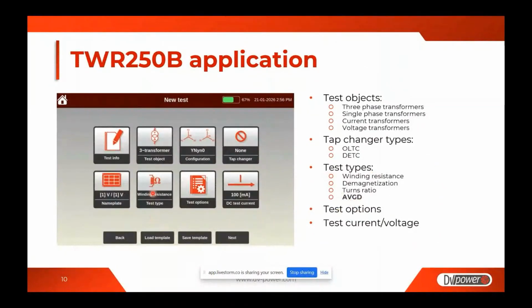So when you select test type, you can select automatic vector group detection, and then the device will be able to automatically recognize the vector group of the transformer. If there is a tap changer, you can select it here, and the nameplate of the transformer can be inserted here. As already mentioned, test types. Here's the list of test types for now. I already explained what we can expect in the short future, and it is test options and test current and voltage, which will be briefly explained in later slides.